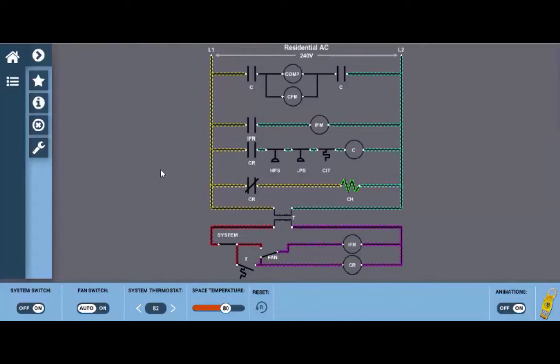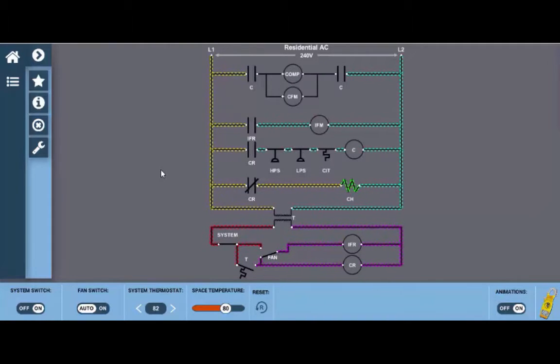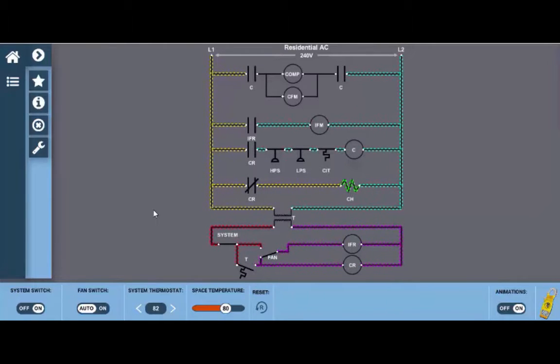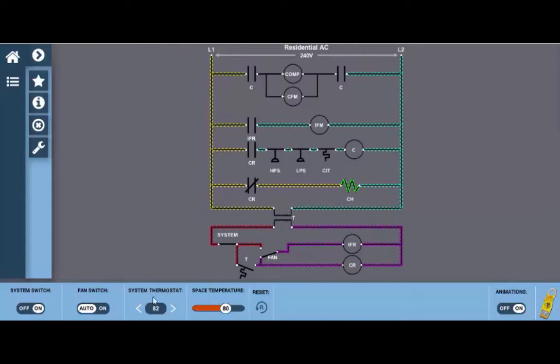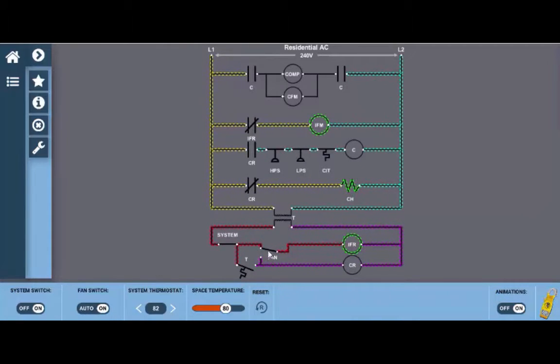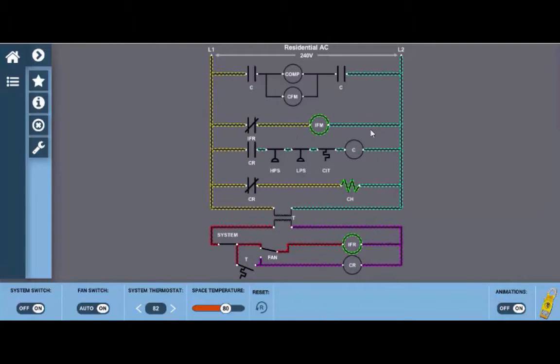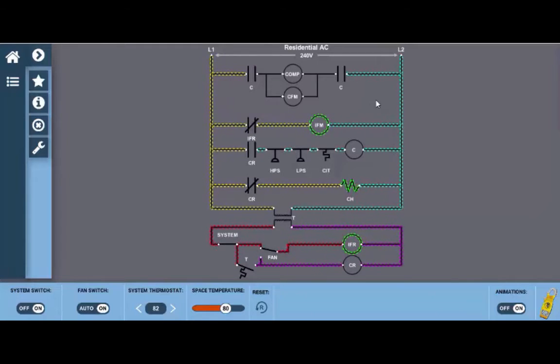This would be a concern if you had indoor air quality issues, primarily filtration that would need to be provided for someone who maybe has allergies or possibly asthma. This would make indoor air quality obviously very important. To do that you just simply click the fan switch to on and when we do that you can see this little fan switch move here and the indoor fan relay coil lights up indicating it's energized and its normally open contacts now close up here providing 240 volts to the indoor fan motor. This is just ventilation mode. The compressor and condenser fan are not operational at this point.